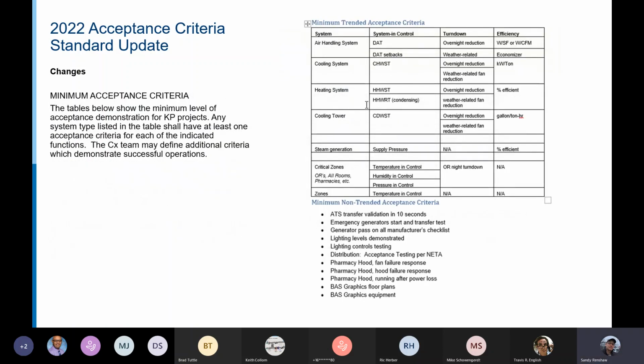So there are certain minimum acceptance criteria, and they've really always been there. We're just trying to call it out because in our audit, we had not seen all of them shown. So you can see the table to the right, which displays the minimum level of acceptance criteria. Any system listed in the table shall have at least one acceptance criteria for each of the indicated functions: system in control, turn down, and efficiency. The commissioning team may define additional criteria which demonstrate successful operations. And minimum non-trended acceptance criteria is right below the table.